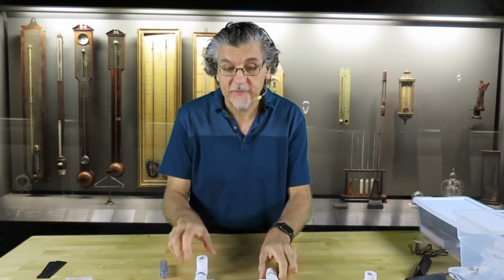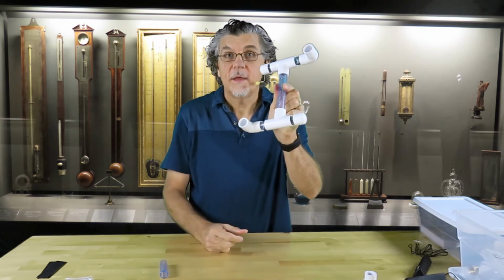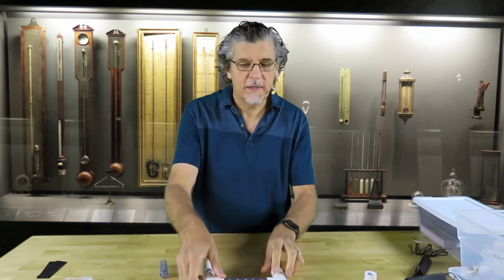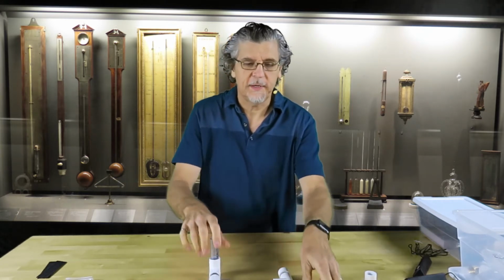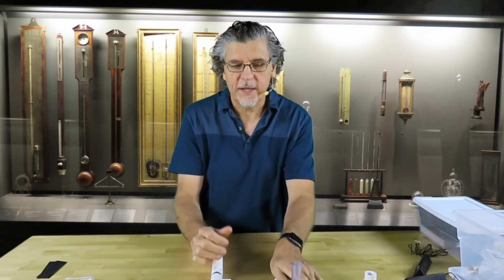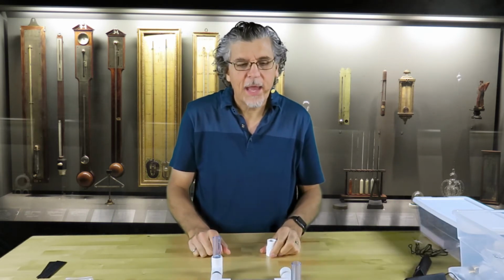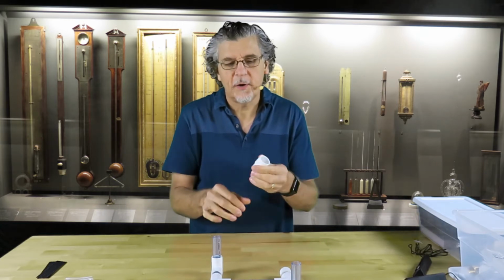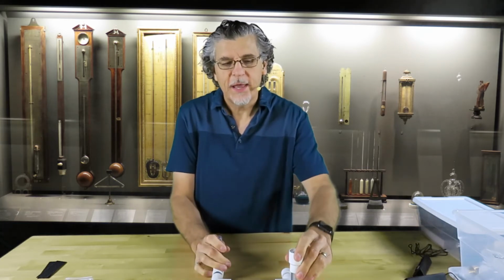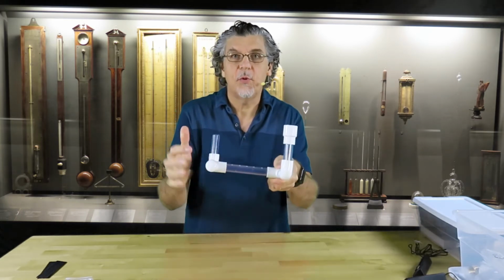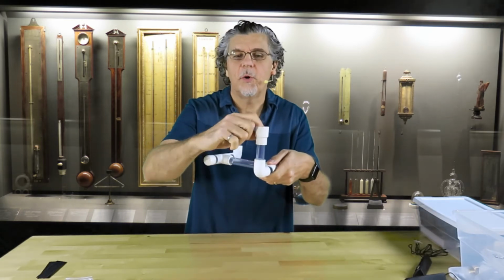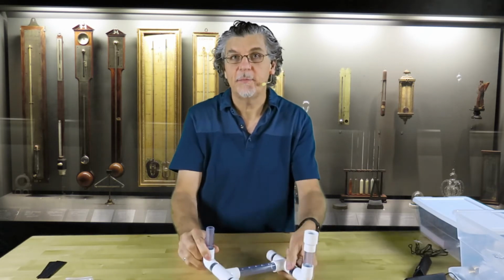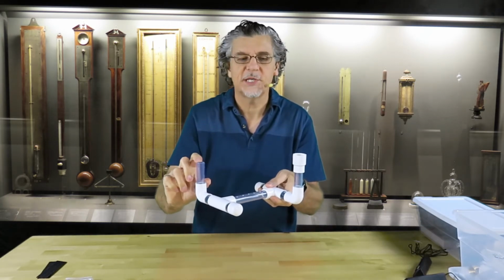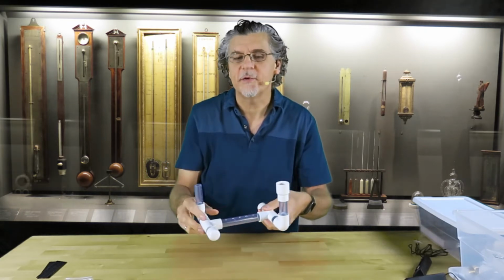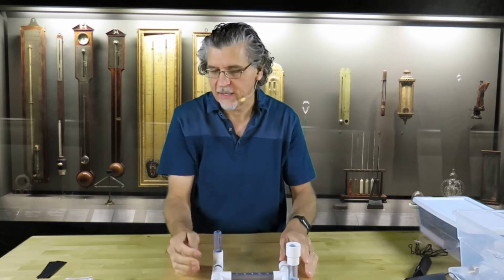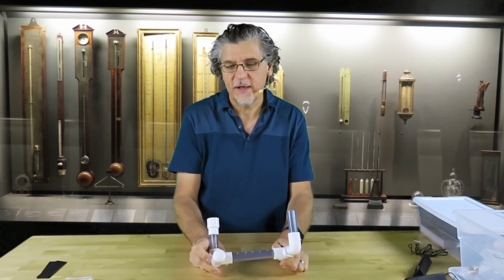Okay, so what we have now is a structure that looks something like this. What we now need to do is put the 3-inch risers in the two 90-degree elbows that are sticking up. And with one of them, we'll put our 3/4 to 1/2-inch adapter. That is where we're going to pour either hot water or cold water for the calibration. Obviously, we will not be able to get to a higher position than here, but it just makes it a little bit easier. It's almost like a funnel. Okay, so that is the apparatus for the calibration.